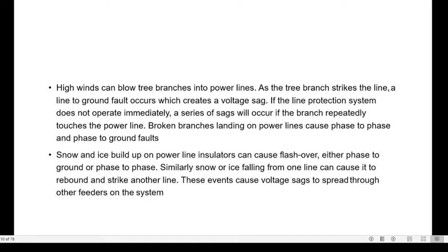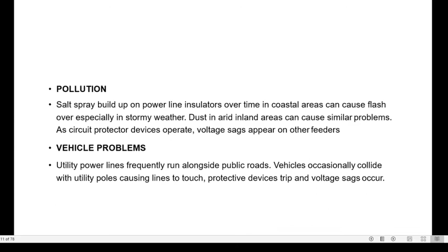From the last lectures we are discussing the causes behind the voltage sag. In addition to the previous causes, one can add pollution, vehicle problems, animals and birds, construction activities. These are certain common natural problems behind the voltage sag. Then also transfer of the loads from one power source to another. Most facilities contain emergency generators as a backup to maintain the power to the critical loads in case of an emergency. Sudden application and rejection of the loads to the generator could create significant voltage sag or swell.